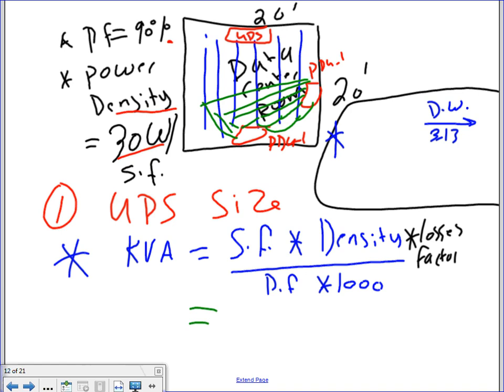One more time. Here's my computer room. Adam, I have a computer room. Can you guys see that? 20 feet by 20 feet. I have a UPS and PDU, exactly like you guys have in our project. I have all these servers and racks, and we're feeding all these racks from PDU1 and PDU2. The density for this data center, the computer engineers that designed the data center told us they're going to put 30 watts per square foot. Every square foot is going to be loaded 30 watts. They are going right now to 200, 300 watts per square foot. The power factor for the system is 0.9, and we're going to fill this 20 by 20 with these computers, and we need to size the UPS for it.